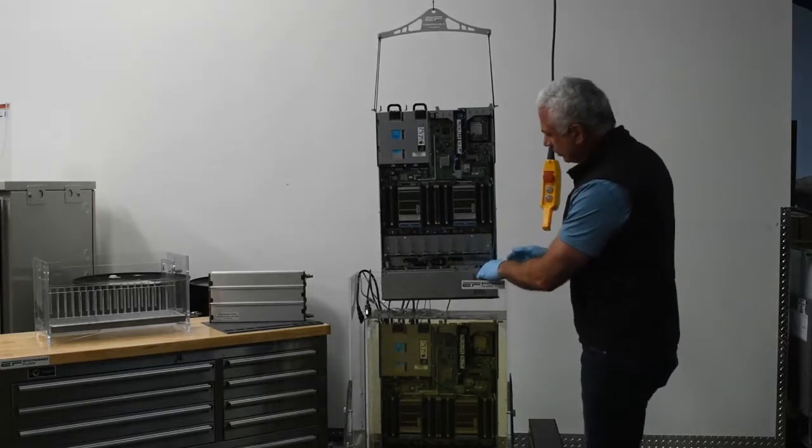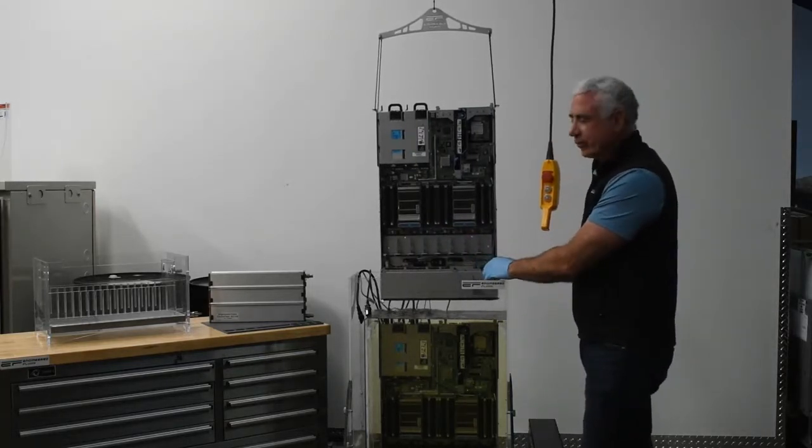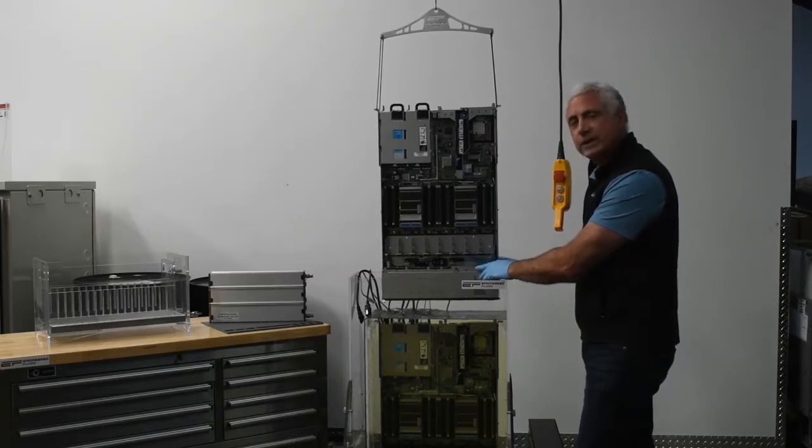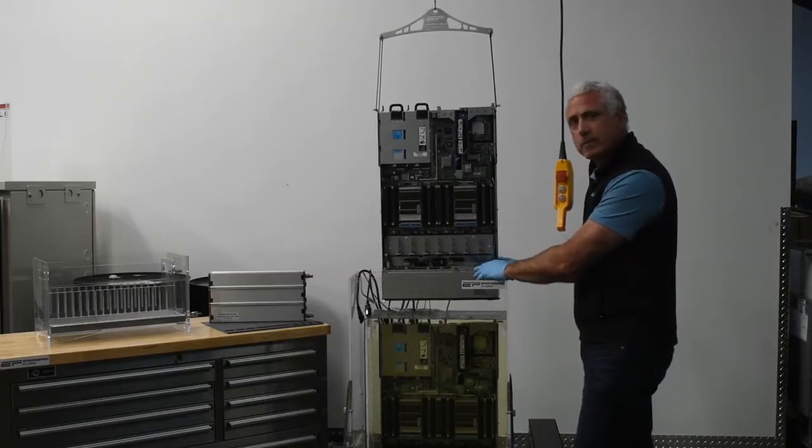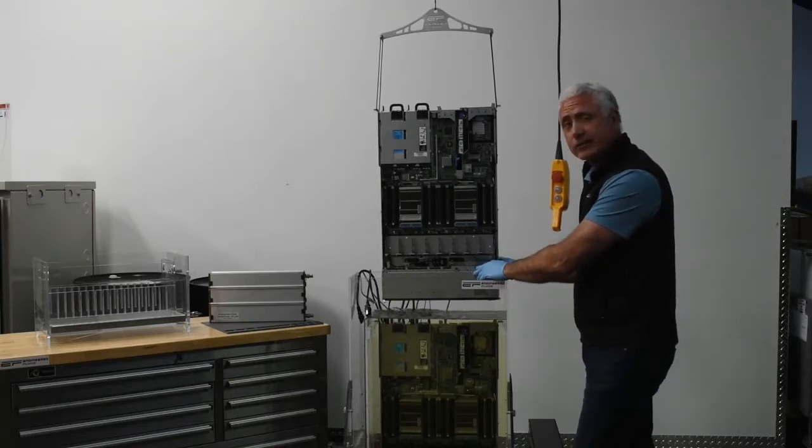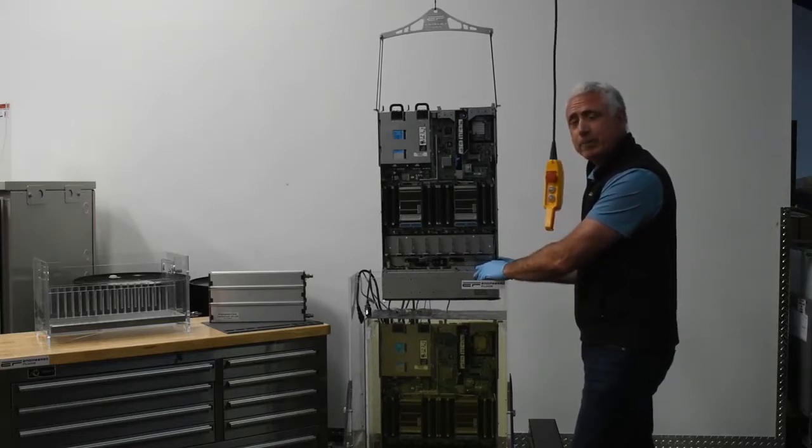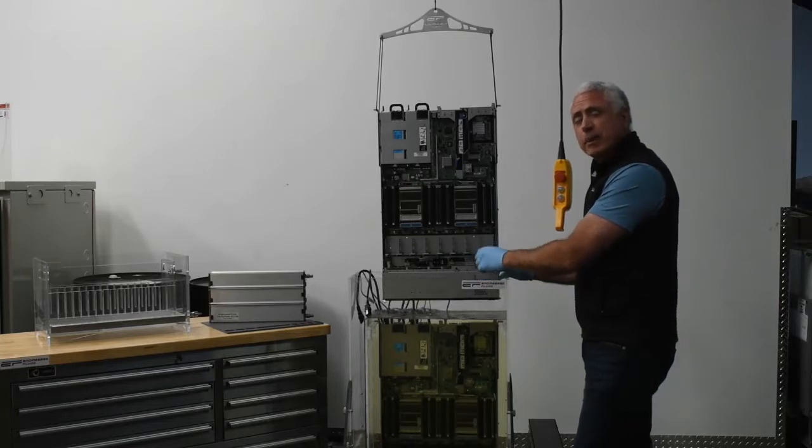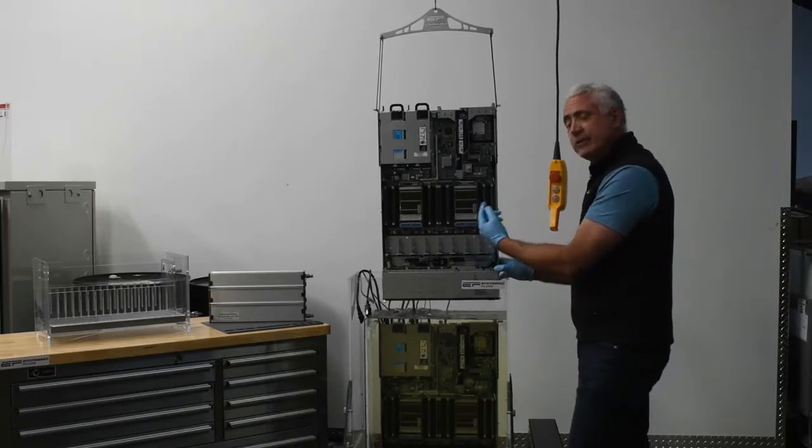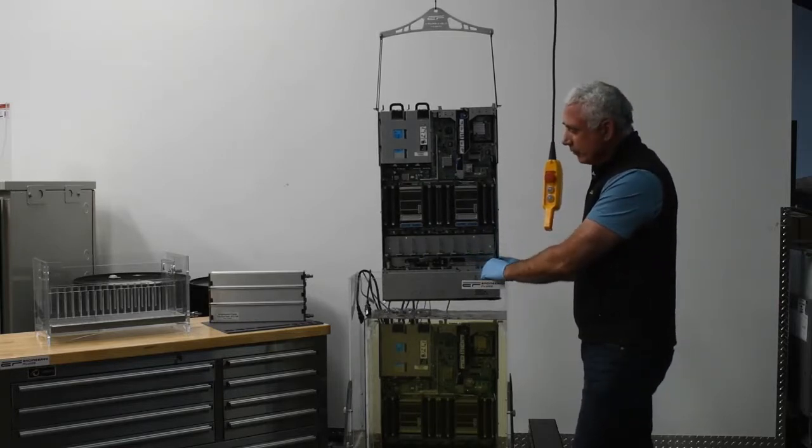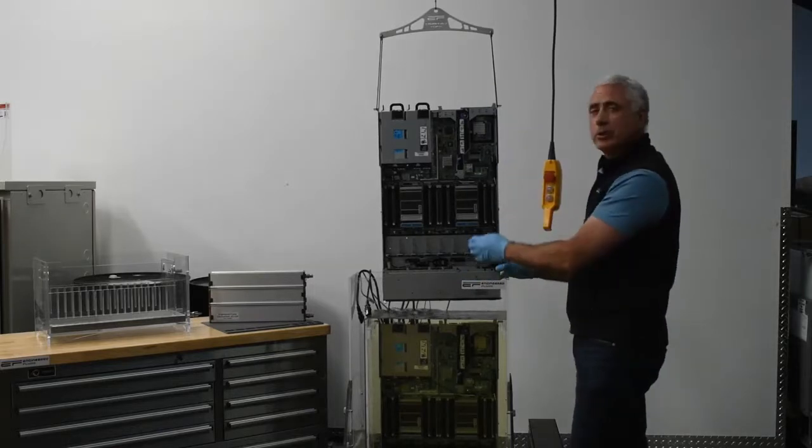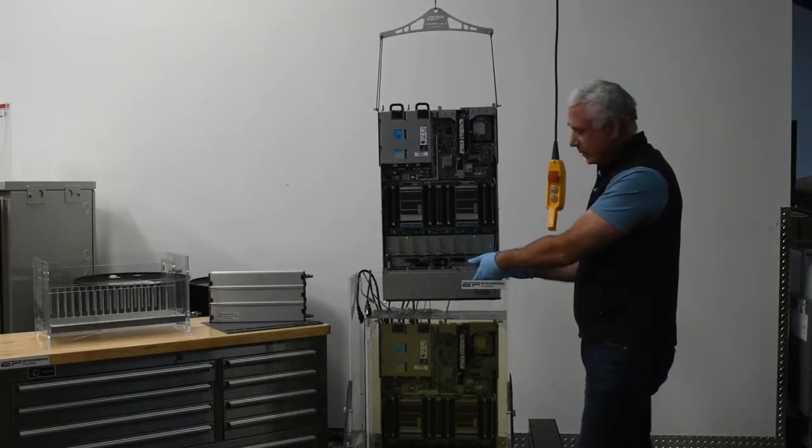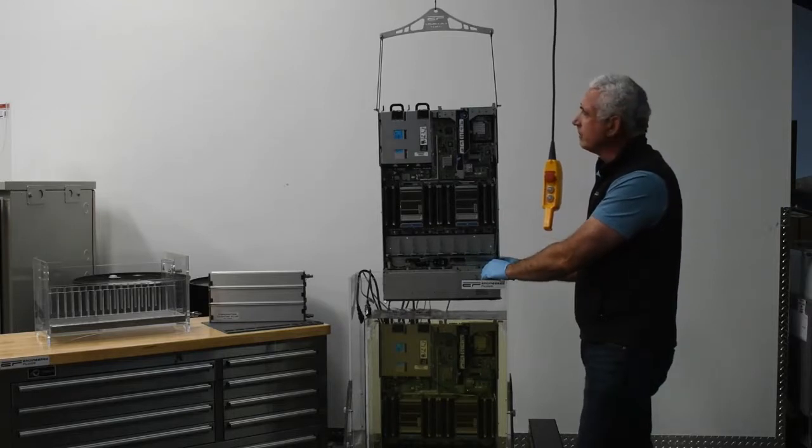We can do the same if we were going to replace the disk drives. In this case this server has solid state drives. We don't put any spinning disks into the fluid. The fluid actually wouldn't hurt the disk, but because they're not designed to operate in a fluid environment you get a bunch of drive errors that occur because the disk starts to spin slower. So in order to replace those we would simply raise the server up a little more and then we would have access to the front of the server.